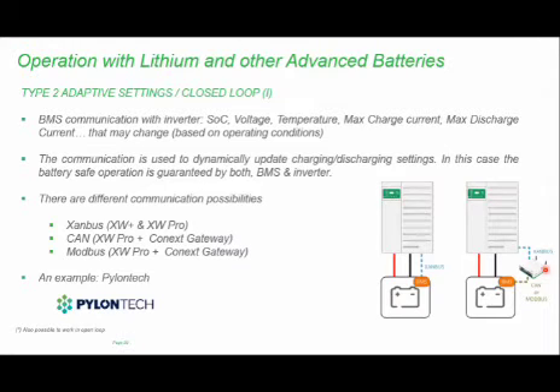On our edge control devices in Schneider for our solar aspects, we have the gateway, we have Insight Facility, we have Insight Cloud. Any of these edge control devices can be used as the interpreter in this aspect. So here, the BMS of the PYLONTECH battery's CAN bus connects to the gateway, because the gateway also speaks CAN bus, Modbus, and the inverter's bus language. You connect it, and at the same time the bus from the battery also connects to the gateway to perform this closed loop integration.